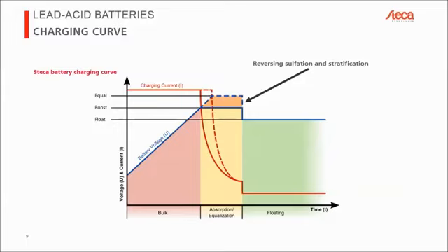the sulfation, the crystals which have built up on the lead plates, will come off. It's as if you paint a piece of metal, and underneath the paint there's some air, and if, for example, there are seasonal effects and the air expands and contracts with temperature, then at some point the paint will come off, because the paint is not completely fixed to the metal surface, but because there's some air in between. That's sort of what's happening here. The crystal is attached to the lead, but because gas is forming between the lead and the crystal, the crystal basically falls off and sinks to the bottom.